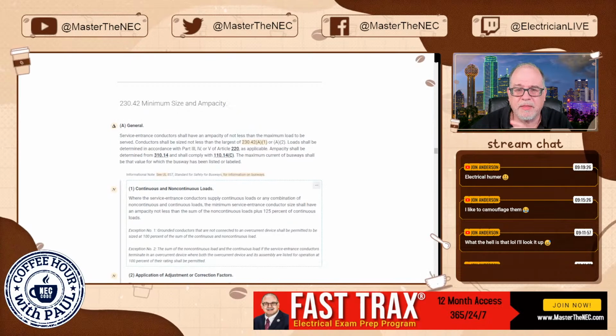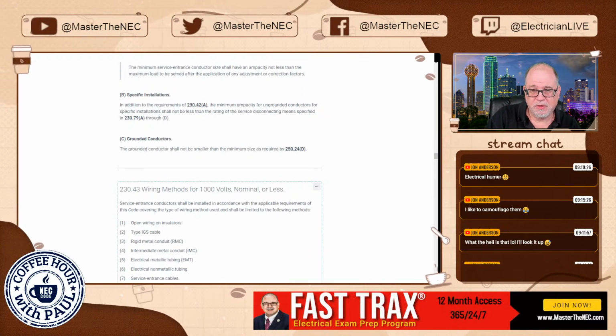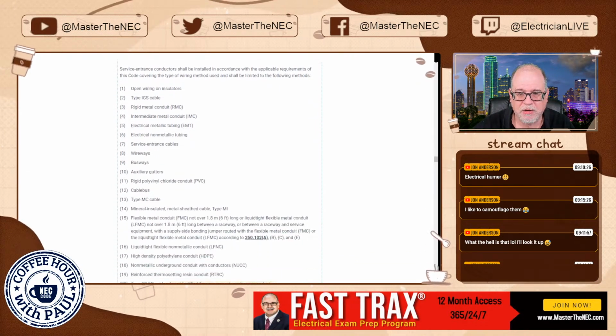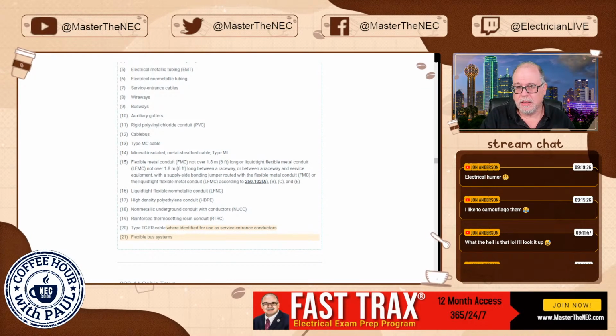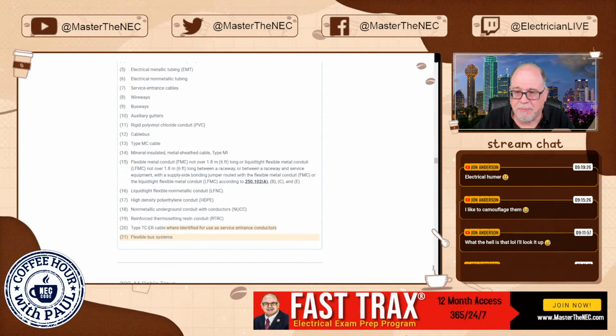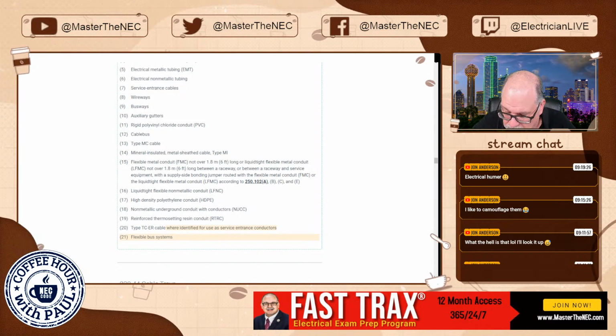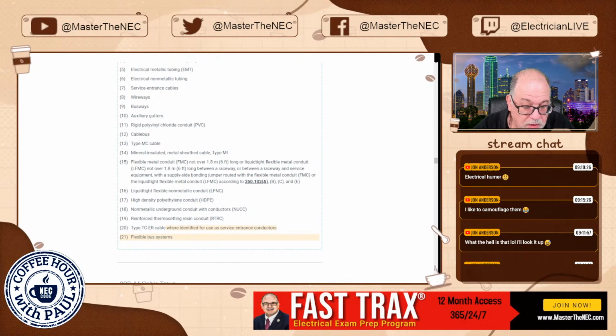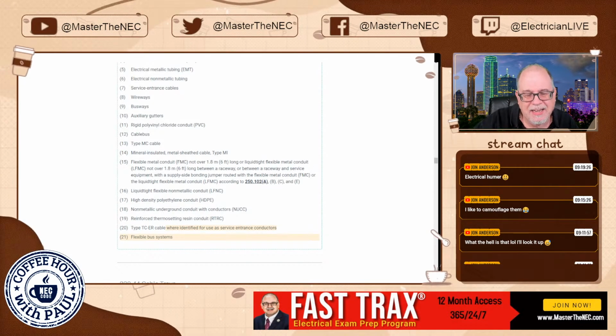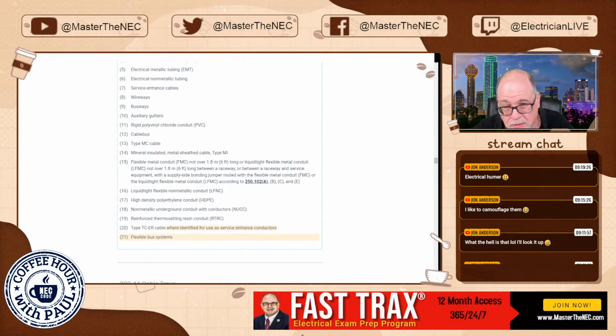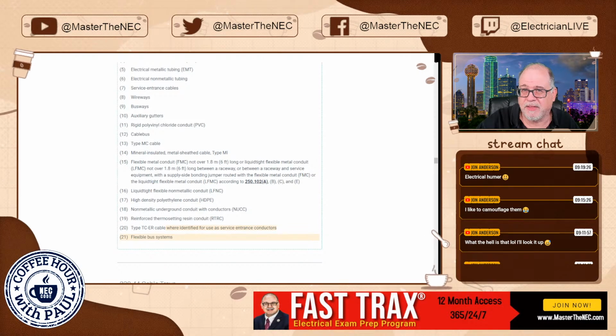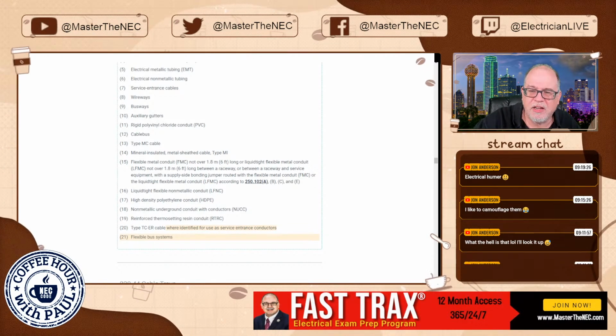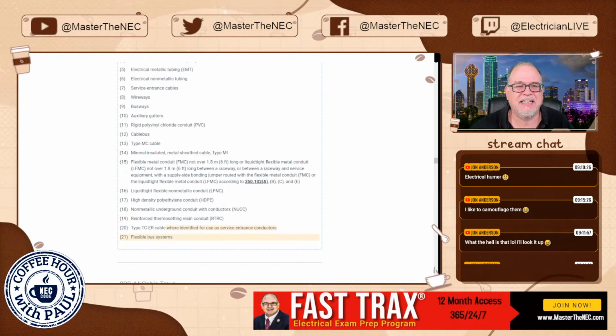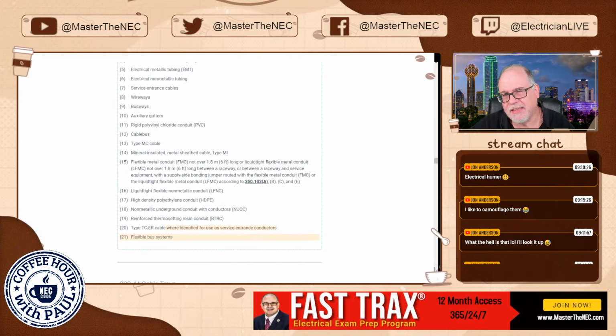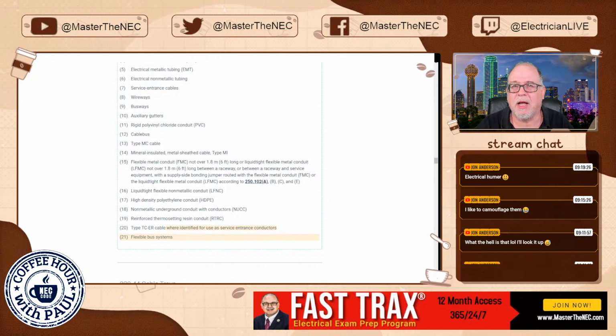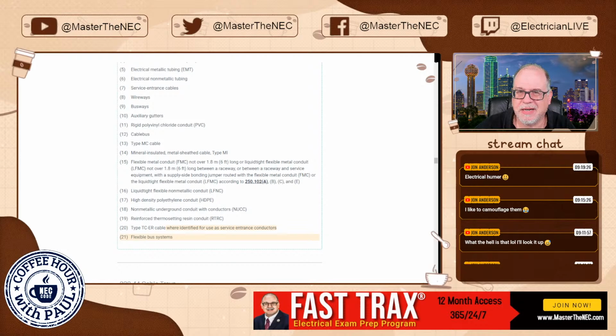230.43. So this one deals with, let's see here, different wiring methods for service entrance conductors. Okay, well, guess what's added here as well? Now, we had tray cable before, but there was nothing in there that I believe stated anything about having to be service entrance conductors or identified as such. And so I'm looking here, and all I saw previously was this type TC-ER cable. Well, we've added now the markings that have to be service entrance conductors. And guess what? Most TC-ER cables are not going to be rated for that because they're not constructed the way service entrance cables would be. So it has to have this identification on it, right? So we've done that. That's obviously the hybrid with Encore meets this rule as well. So again, run out and get you some of that hybrid cable, right?